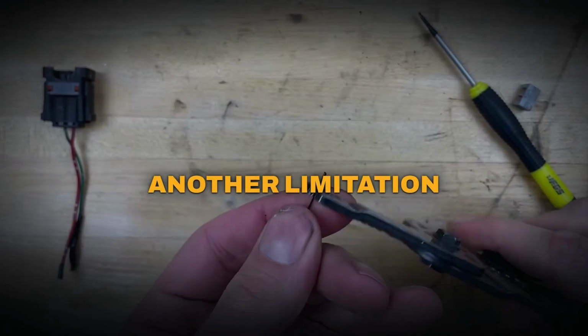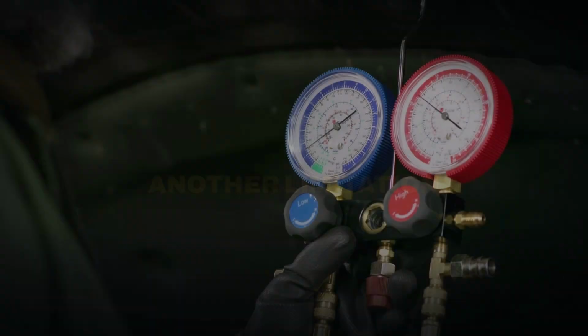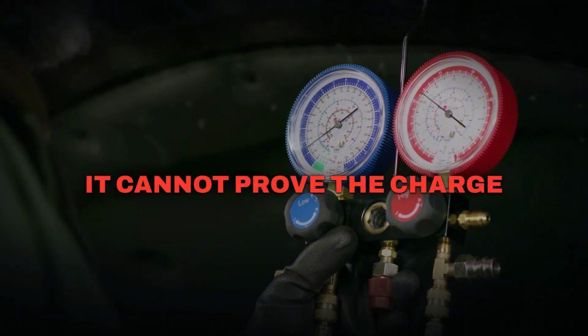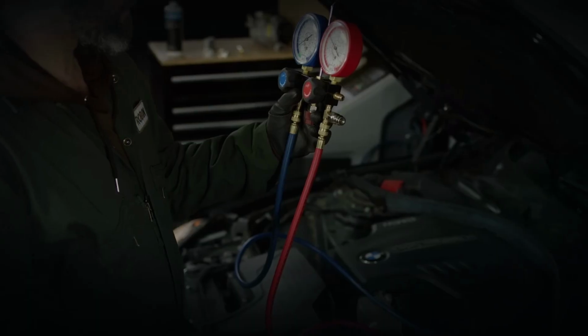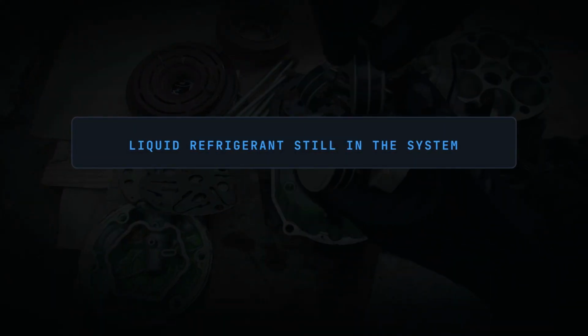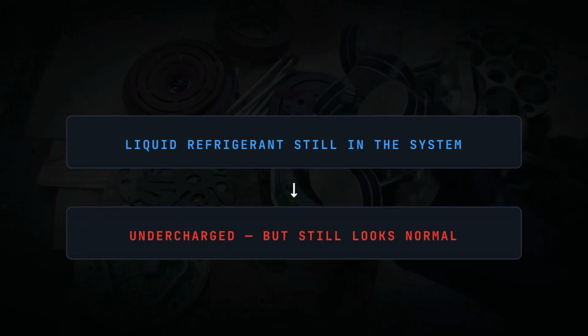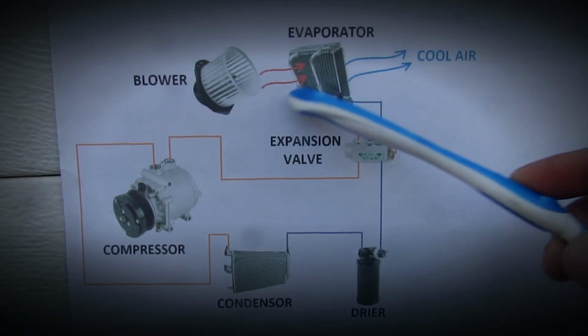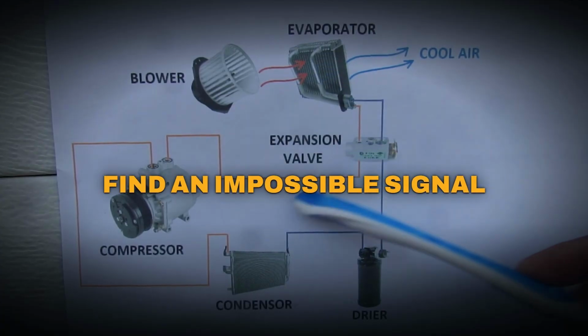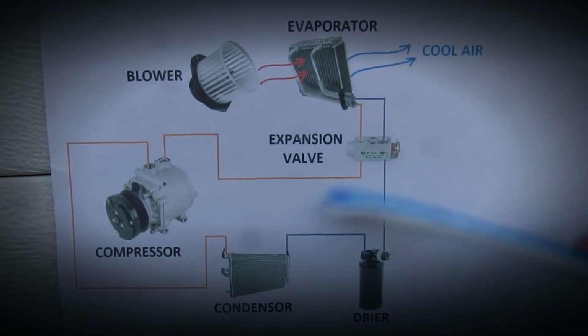There is another limitation many people miss. Static pressure cannot tell you whether the system contains the correct refrigerant charge. As long as liquid refrigerant remains, an undercharged system may still show a believable static pressure. Use this check to identify an impossible signal, not to approve the refrigerant charge.